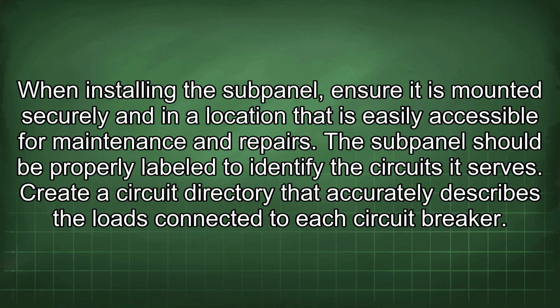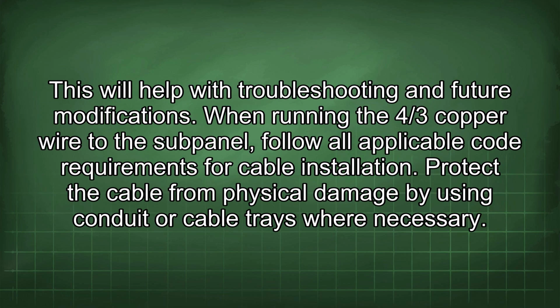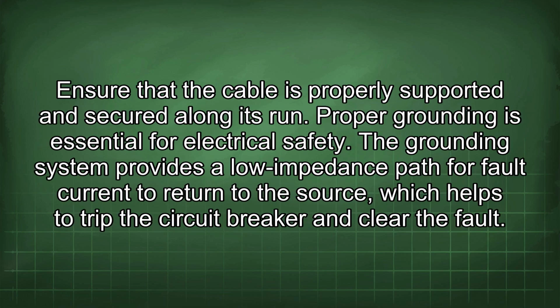When installing the subpanel, ensure it is mounted securely and in a location that is easily accessible for maintenance and repairs. The subpanel should be properly labeled to identify the circuits it serves. Create a circuit directory that accurately describes the loads connected to each circuit breaker. This will help with troubleshooting and future modifications. When running the 4/3 copper wire to the subpanel, follow all applicable code requirements for cable installation. Protect the cable from physical damage by using conduit or cable trays where necessary. Ensure that the cable is properly supported and secured along its run.